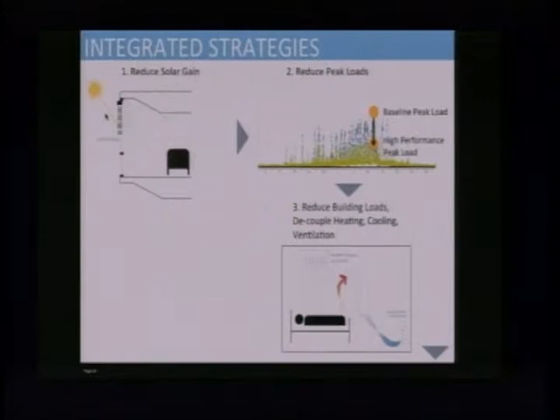systems. So in this case, for Targeting 100, we chose to use a displacement ventilation system with radiant heating and radiant cooling. That's just one way to do this, but essentially at the core, we want to decouple the heating and cooling from ventilation. And we're not able to do that unless we reduce that solar heat gain in the room. Displacement ventilation wouldn't work, and the radiant cooling panels would not be able to keep up with the higher peak load. We'll talk a little bit about that later when we look at the data.